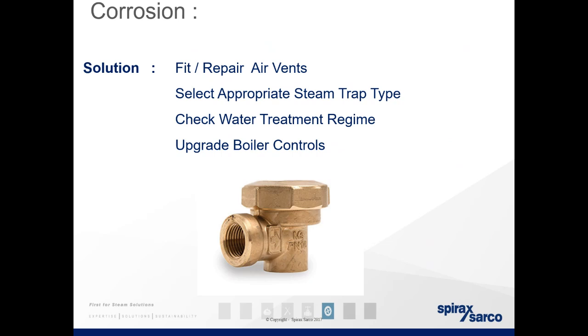So the solutions are to fit and repair air vents, and to select appropriate steam trap types. We have different steam traps for different uses in the industry, not just in Spirax. And check your water treatment regime. Make sure that you're only dosing what you need to, not overdosing your steam system. And upgrade boiler controls. For instance, on-off pump controls can be changed to modulating, so there's less thermal shock on your boiler. TDS controls, so automatic TDS blowdown, automatic blowdown on your boiler. These are things that we can change to increase efficiency. Are there any questions before I move on?